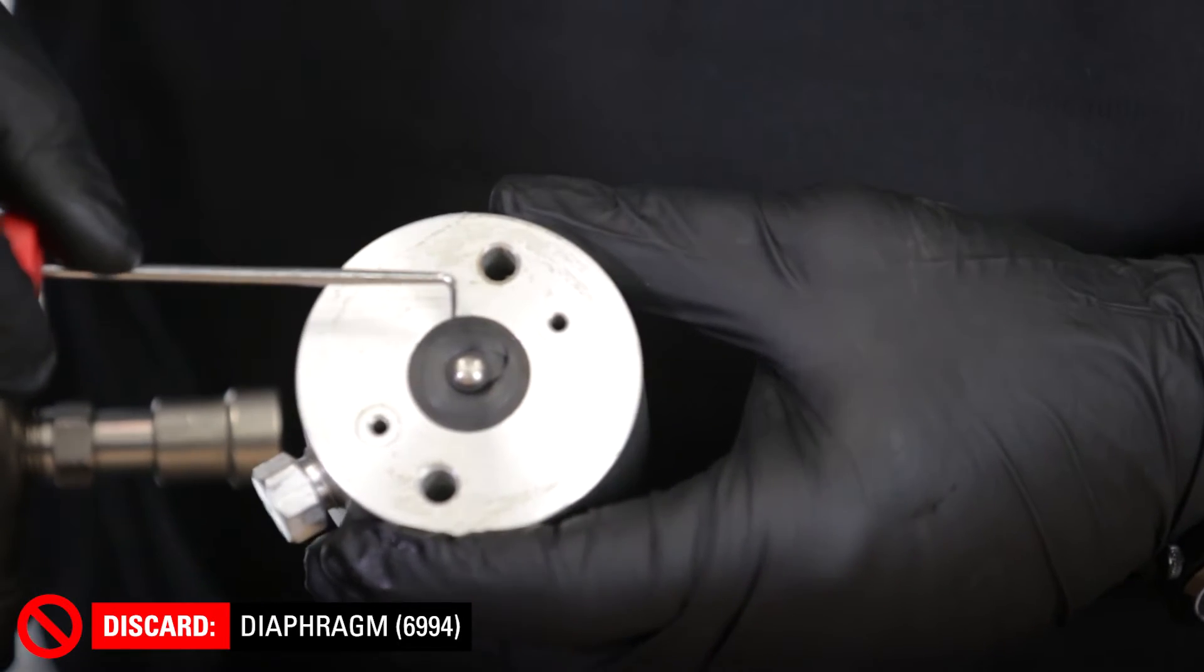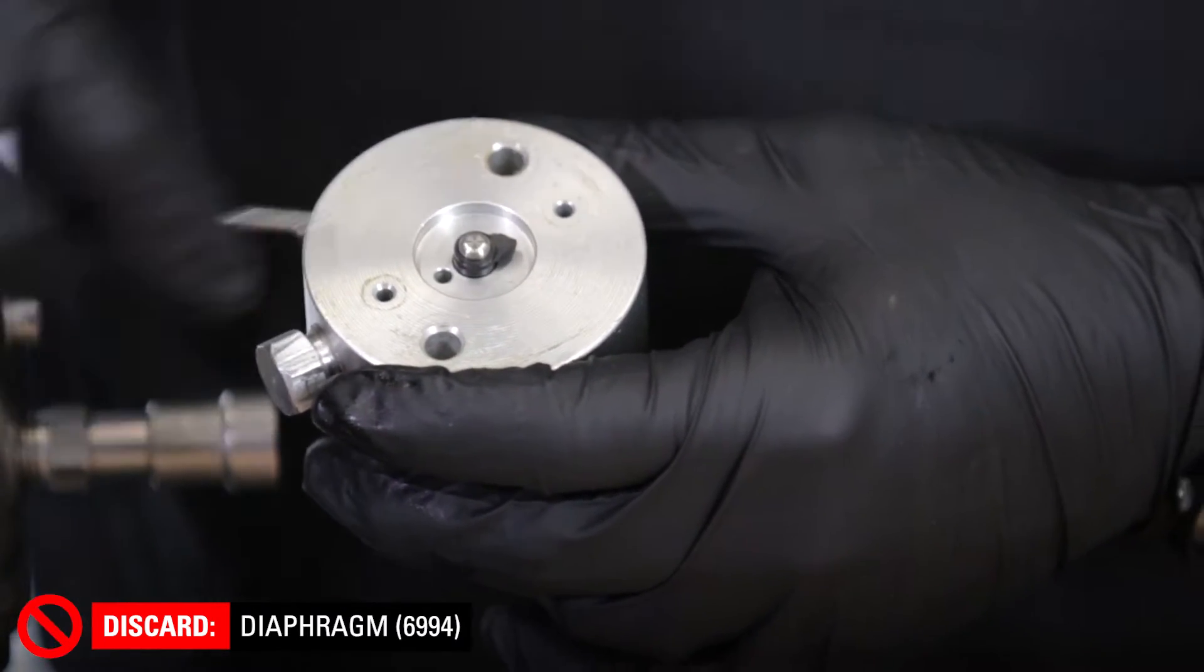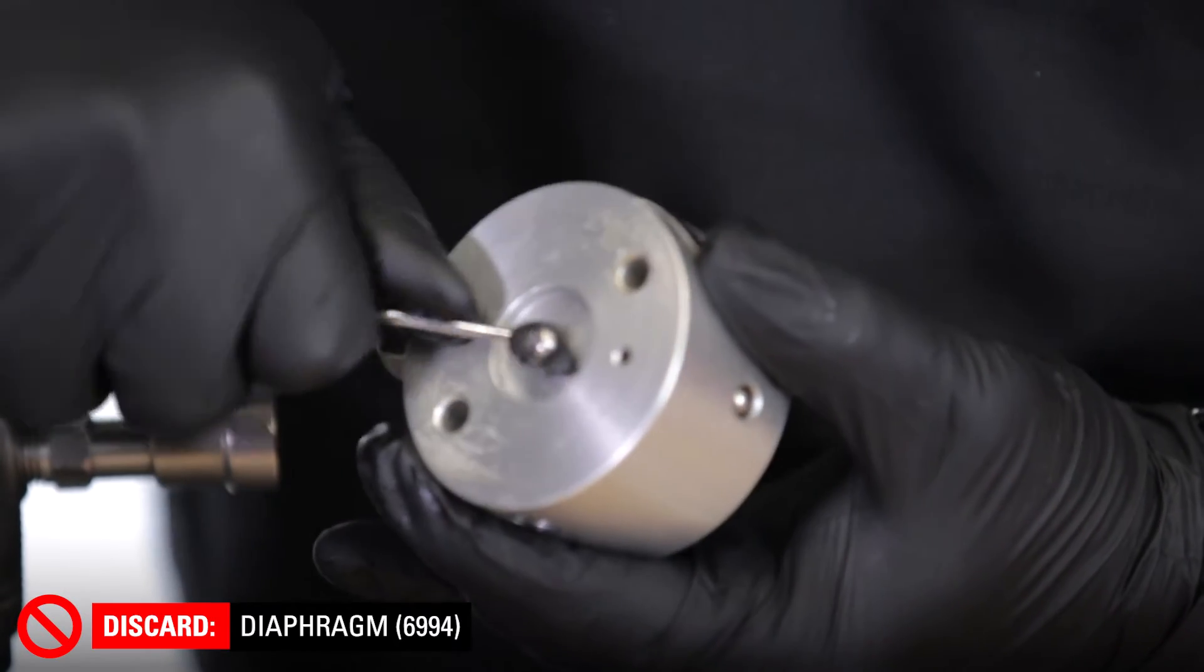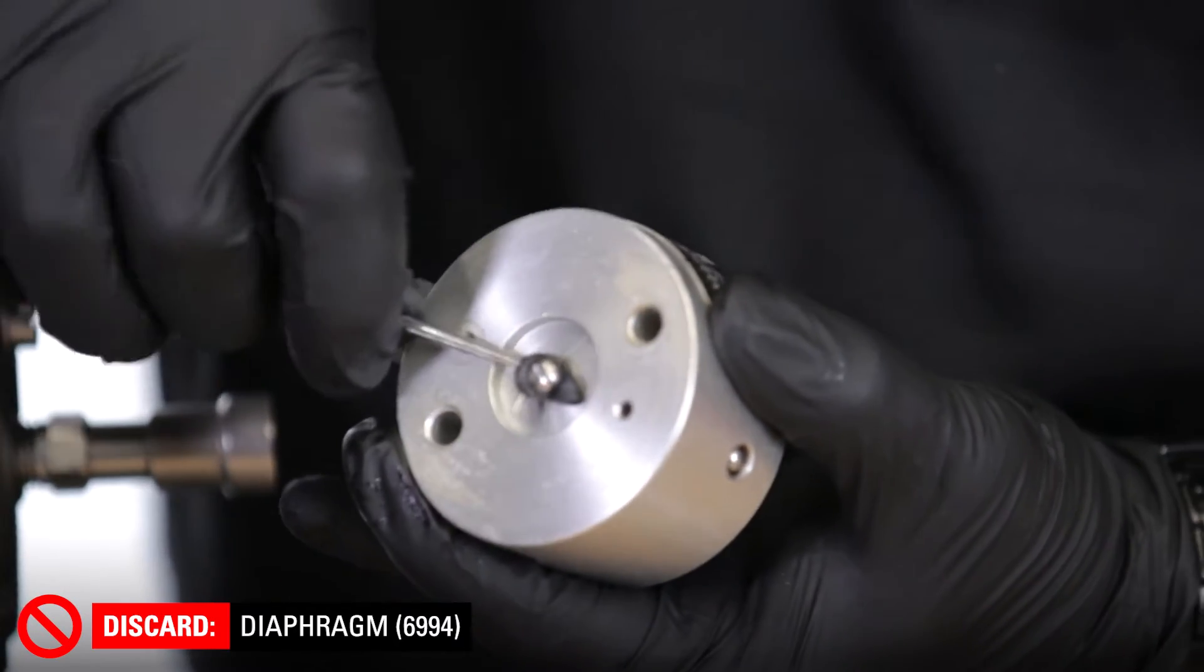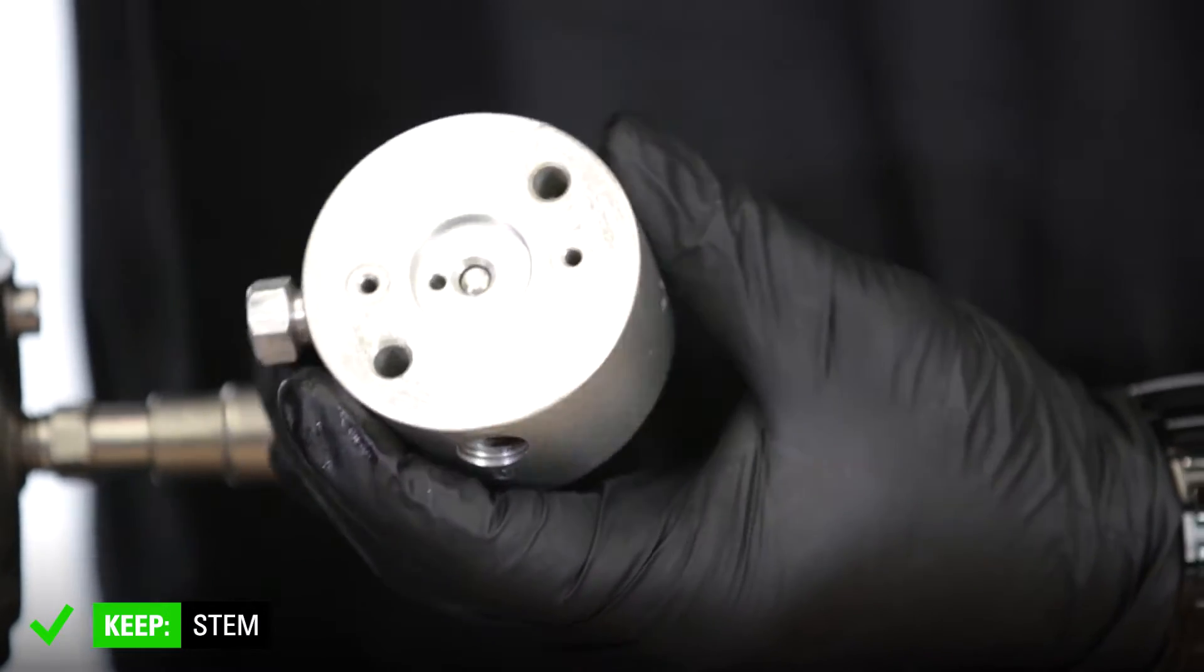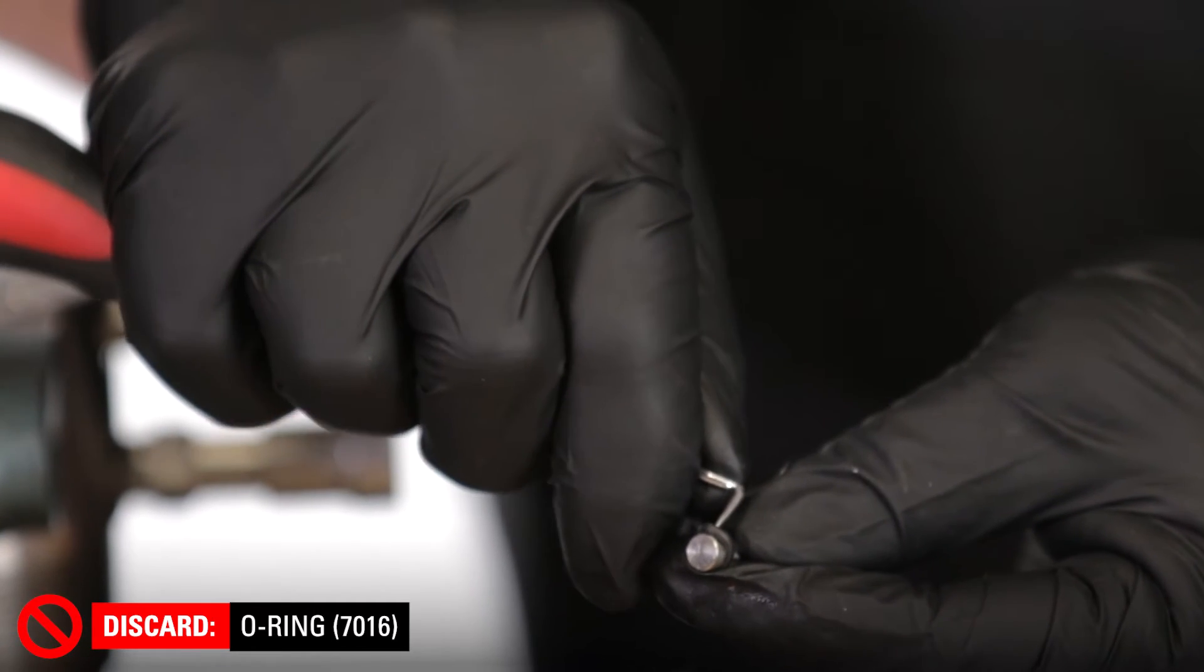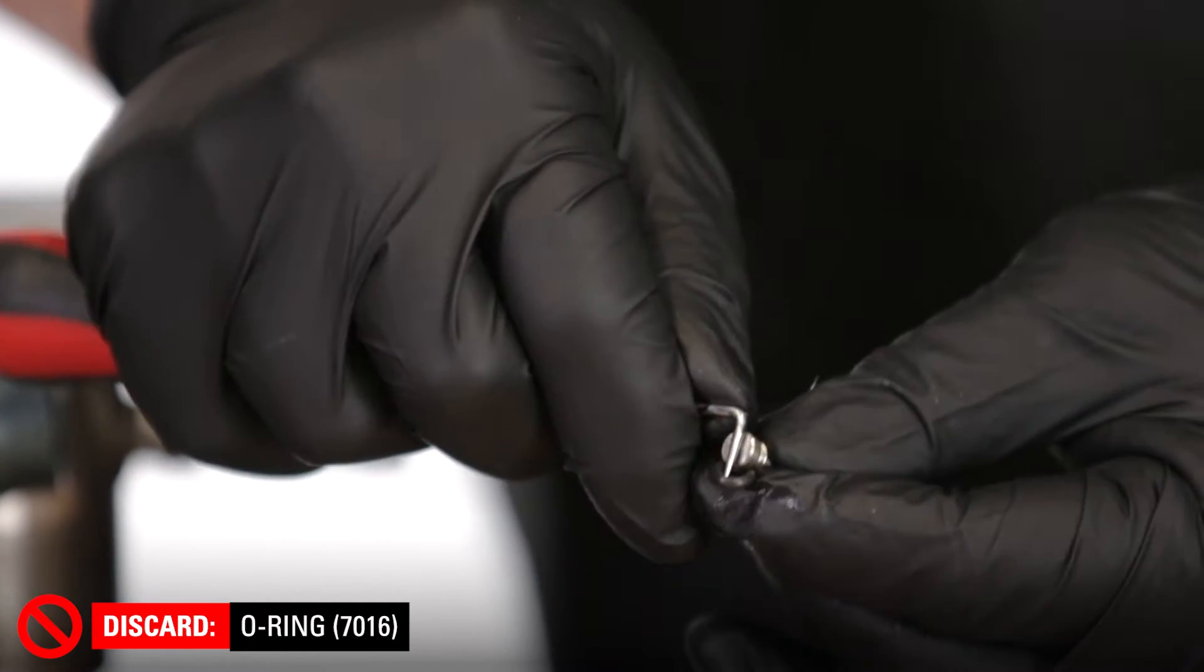Remove the diaphragm by using a pick to lift it. This piece will be discarded, so if you damage it during the process, that's okay. Be aware once the diaphragm is removed, the stem may fall out of the body. Keep the stem to reuse. Discard the O-ring from the stem. Then set the stem aside.